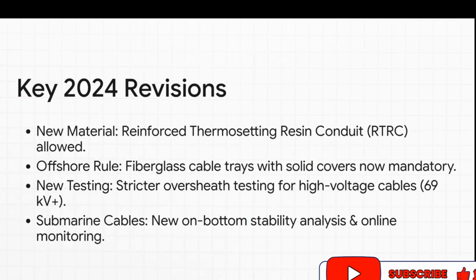And you gotta stay current, because this document changes. The February 2024 update had some huge changes you need to know about. For example, RTRC conduit is now allowed underground. If you're offshore, you're now required to use fiberglass trays with solid covers. Testing for high voltage cables got even stricter, and there are totally new rules for submarine cables. Knowing these latest changes is a huge advantage.